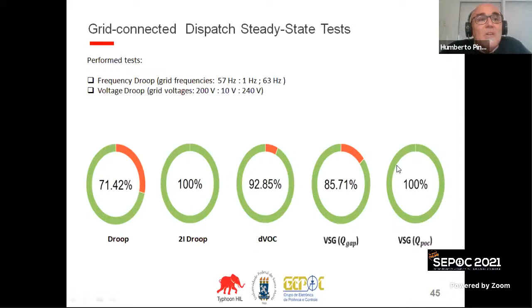We have two alternatives for the virtual synchronous generator: either feedback of the reactive power on the gap, or feedback of the reactive power at the point of common coupling. We see that the latter has a better result.